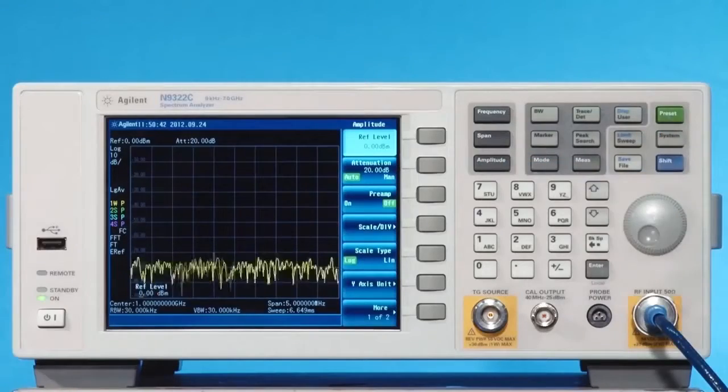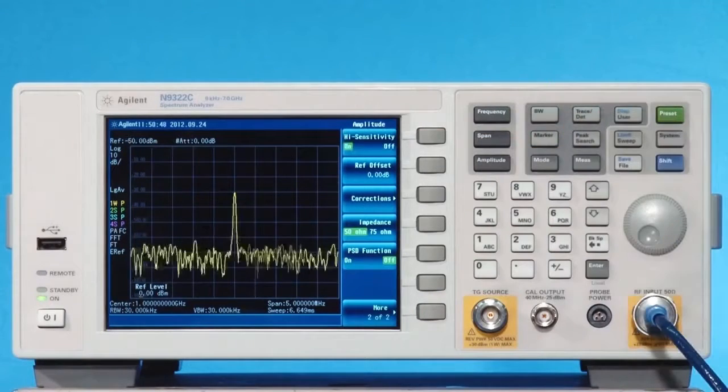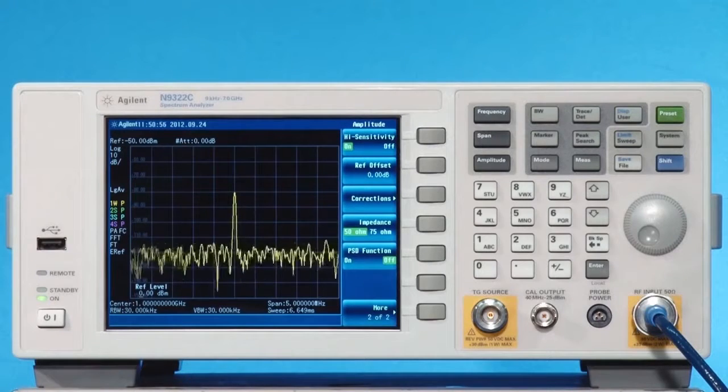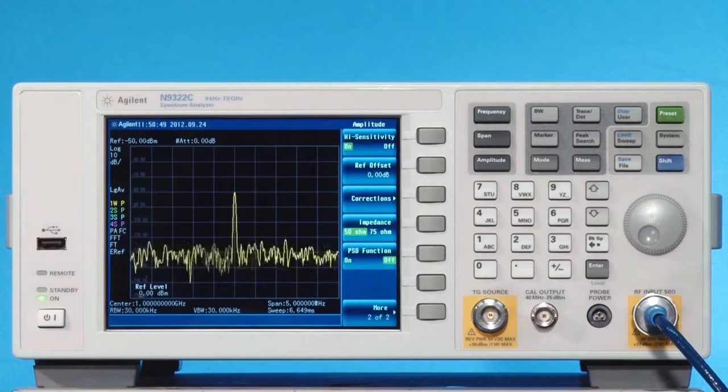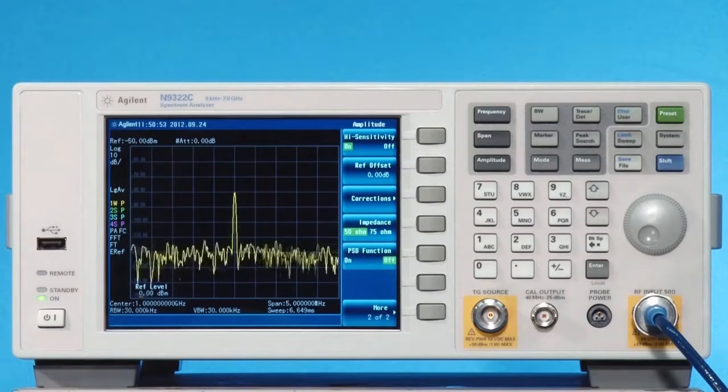Simply push Amplitude and High Sensitivity. You've instantly set the N9322C BSA Spectrum Analyzer's sensitivity measurement status with minus 50 dBm reference level, 0 dB attenuator and pre-amplifier enabled.